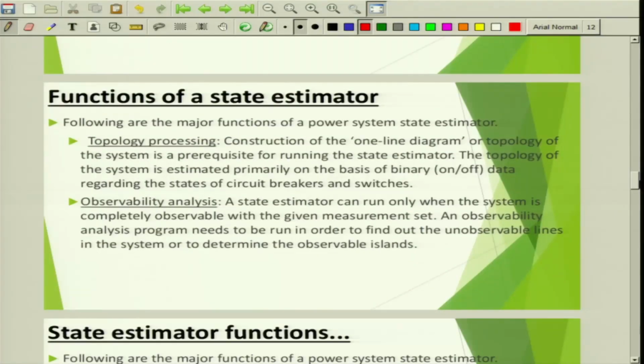Following are the major functions of a power system state estimator. One is topology processing and observability analysis. Construction of the one line diagram or topology of the system is a prerequisite for running the state estimator. The topology of the system is estimated primarily on the basis of binary on or off data regarding the states of circuit breakers and switches. First, you take the blueprint of the entire network, and then based on the on or off condition of circuit breakers, the updated network topology is identified.